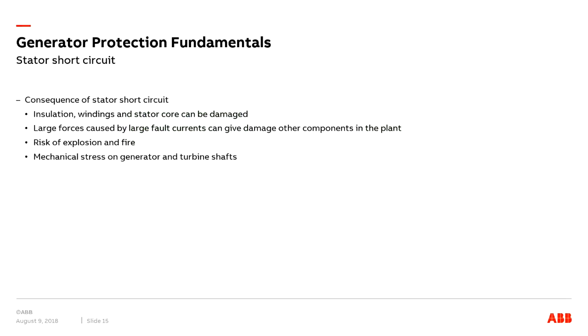So now let's look at the different types of protection in a little more detail. The first one is the stator short circuit protection. Phase-to-phase short circuits in a generator are relatively rare, but when such faults occur, the consequences are severe. When the short circuit occurs, the insulation is damaged. During the fault sequence, the local heating caused by the fault current will further damage the insulation. And in addition, the windings in the stator core will get damaged.